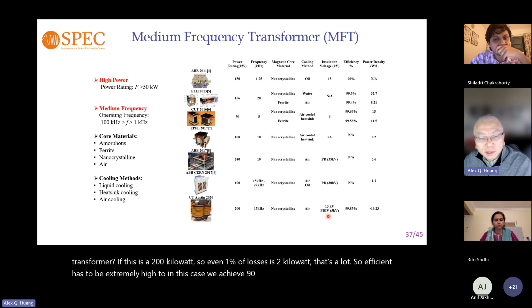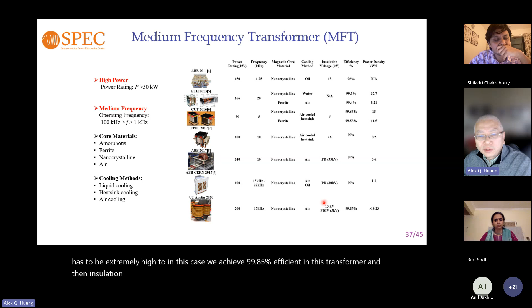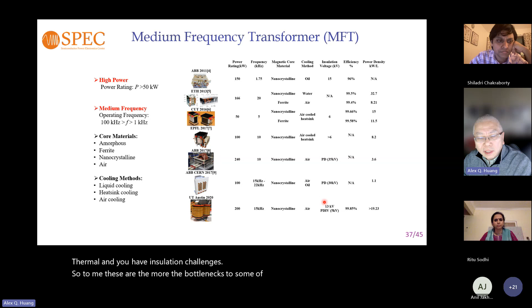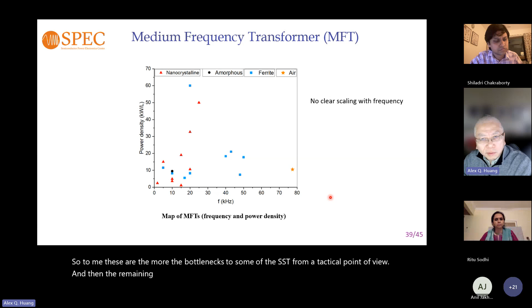That's a lot, so efficiency has to be extremely high. In this case, we achieve 99.85% efficiency in this transformer. Then insulation is the third challenge. So basically, you have electrical, thermal, and insulation challenges. To me, these are the bottlenecks of SST from a technical point of view. The remaining one is cost and reliability. Many people think going to higher frequency is good, but these three major things are limiting you. You need high efficiency, good heat removal, and high insulation. So your design is really constrained.